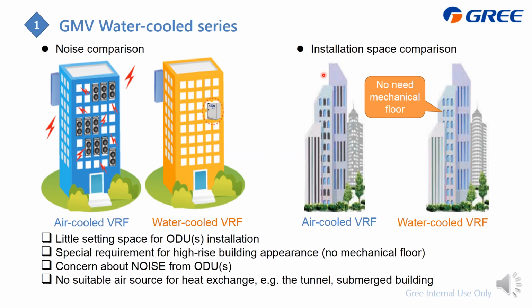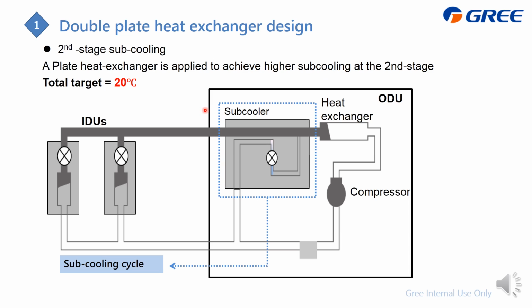And also, if you have some special requirement for the building, for example, all glass without a service floor, for water cool it is available. And also it's easier to install. And for the refrigerant cycle, they are very similar. And we also adopt the subcooler to achieve deep subcooling.